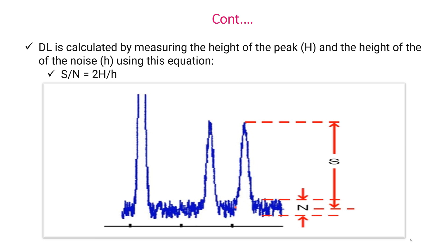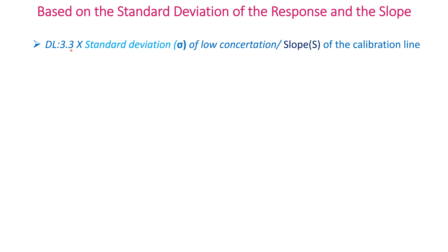In this chromatogram, capital H is the height of the peak and small h is the height of the noise. S/N is calculated as 2 × H ÷ h. DL can also be calculated based on standard deviation of the response and the slope: DL = 3.3 × σ ÷ S, where σ is the standard deviation of low concentration responses and S is the slope of the calibration line.